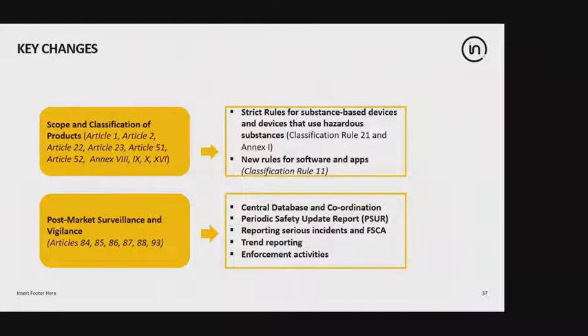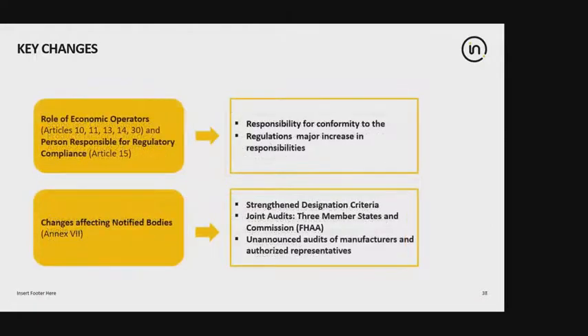Now, key changes. The scope and classification under the medical device regulation has changed with respect to the earlier directive, and the manufacturer has to ensure compliance to the new rules, because the classification of some of the devices has changed compared to the old directive. More emphasis has been given to post-market surveillance and vigilance reporting on the device. Now, manufacturers of class 3 or class 2B implantable devices have to publish a periodic safety update report through the notified body, and this information would be available on EUDAMED.